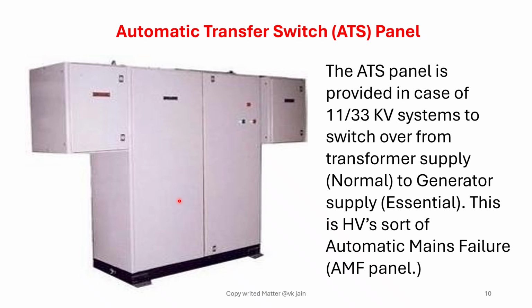This is an automatic transfer switch panel, automatic ATS panel. The ATS panel is provided in case of 11 or 33 kV system to switch over from transformer supply to generator supply. This is a high voltage sort of automatic mains failure, AMF panel.